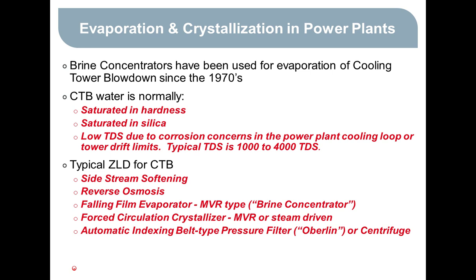MVR stands for mechanical vapor recompression, and we'll talk about what that is in a minute. But it's basically a compression-driven or electric power-driven evaporator rather than a steam-driven evaporator. And it's sometimes called a brine concentrator. That's another term you'll see used.